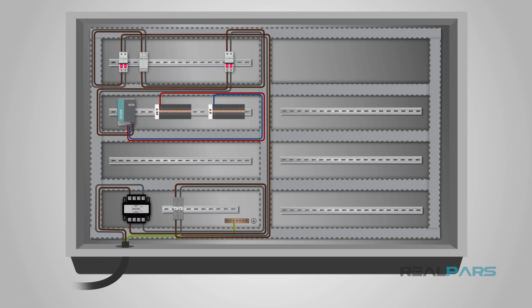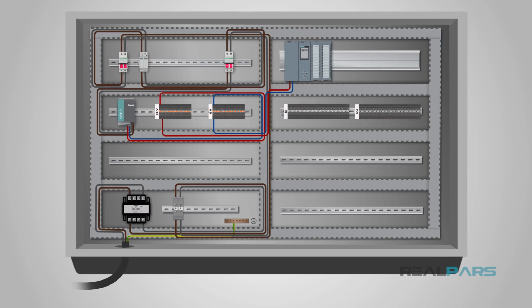The final part of the control panel are the devices that control and monitor the mechanical process. Let's talk about the PLC, or Programmable Logic Controller. The PLC is like the brain of the entire process. The PLC will have a CPU where the logic program is stored. It will have associated inputs and outputs, which will help control and monitor the assembly line. Speaking of our terminal blocks, we will have wires running from them to our inputs and outputs. This allows for the actual control of the assembly line.